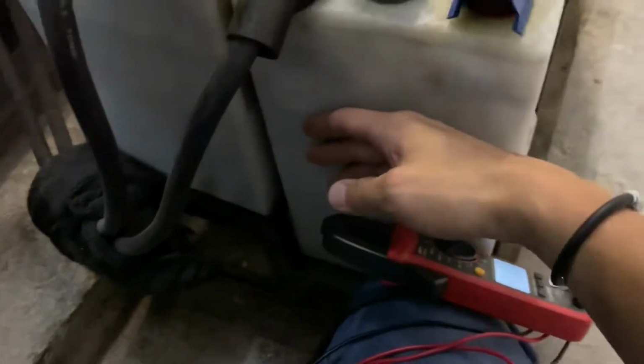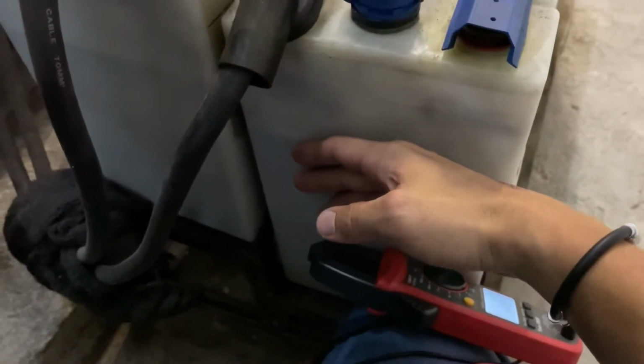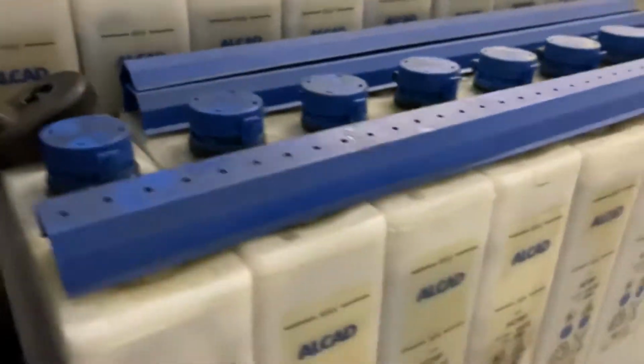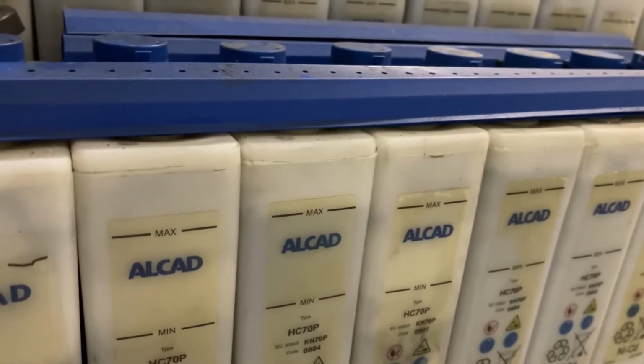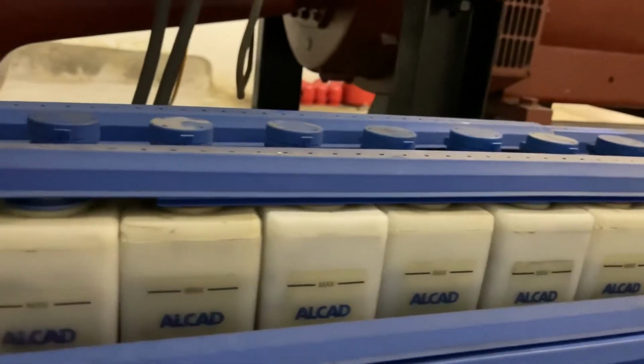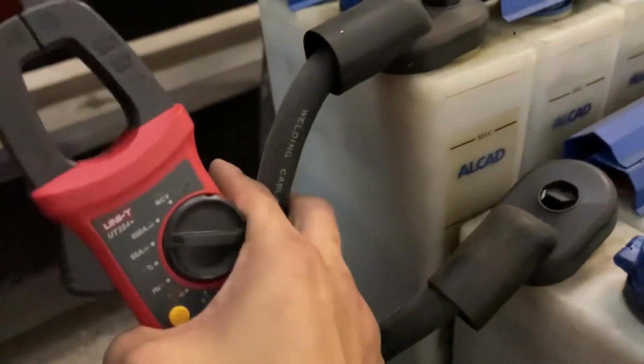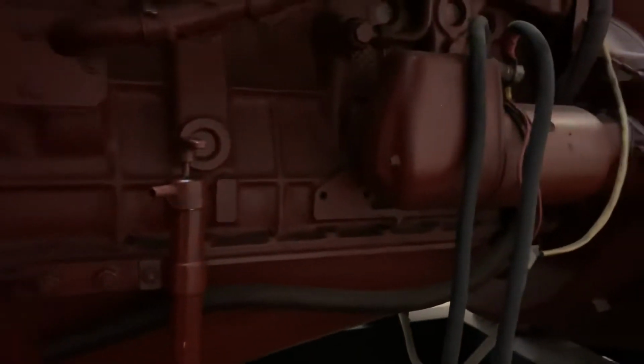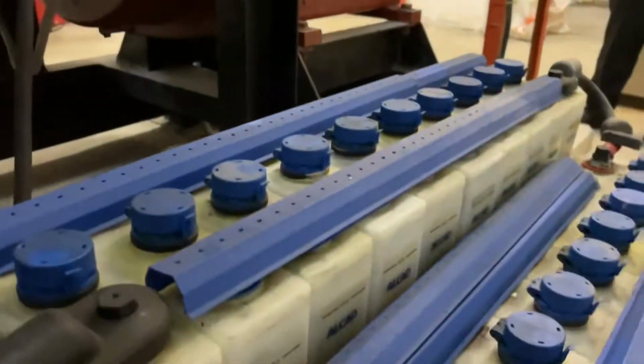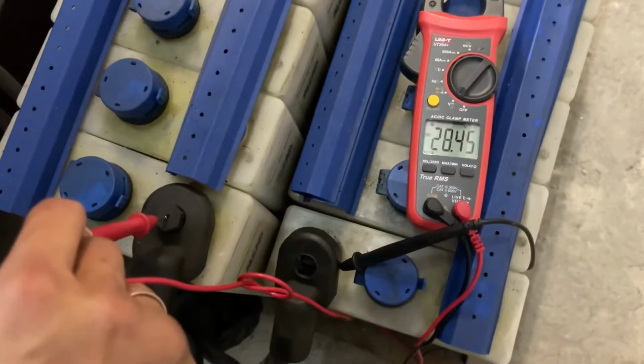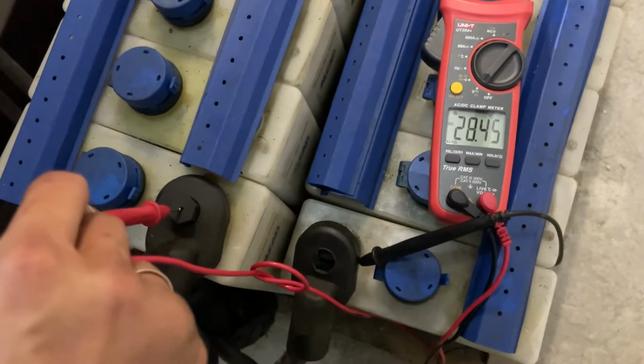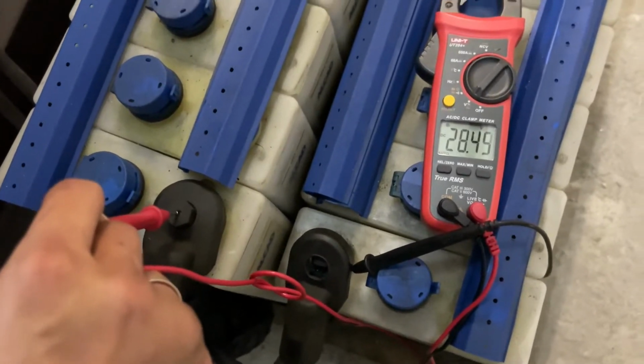And also feel the temperature of the battery. Make sure it's under room temperature, no overcharge or abnormal temperature. Do check the water level is in good condition. Okay, termination, no loose, no oxidization. Alright. From here I get a voltage of 28.45 volt, which is optimal for a nickel cadmium battery.